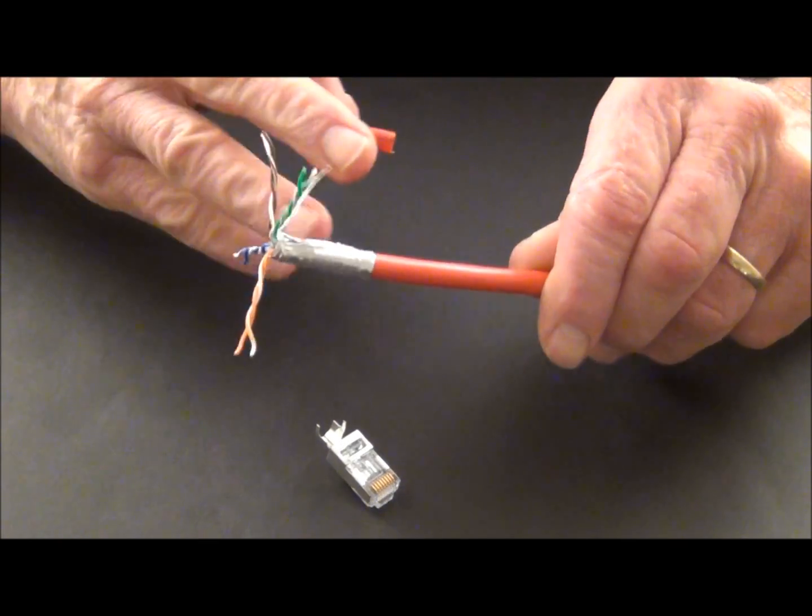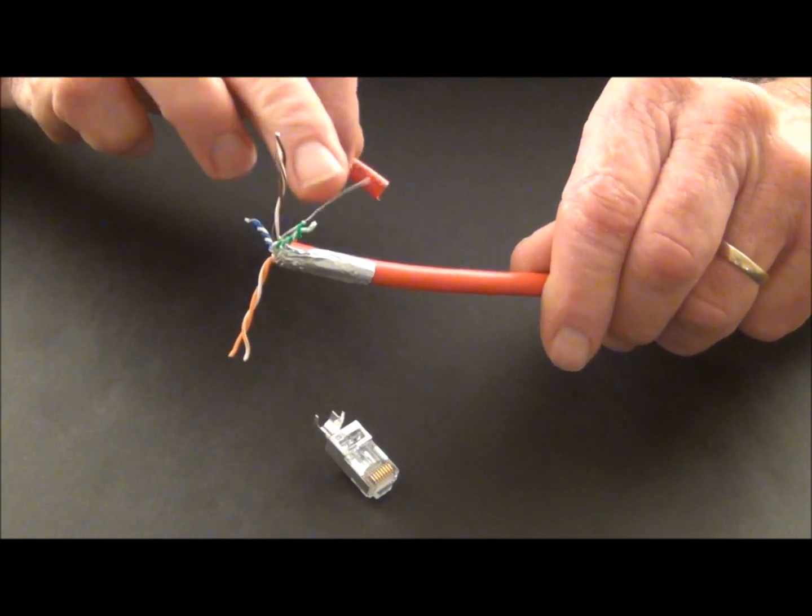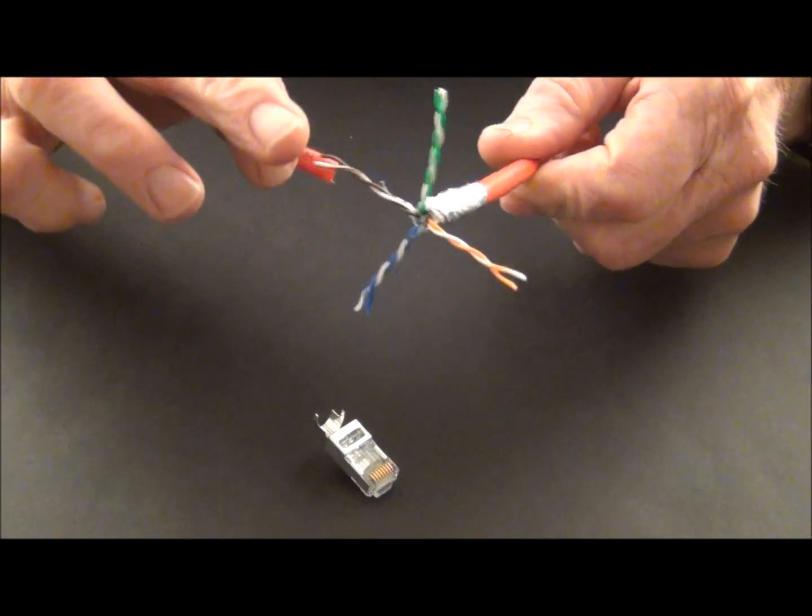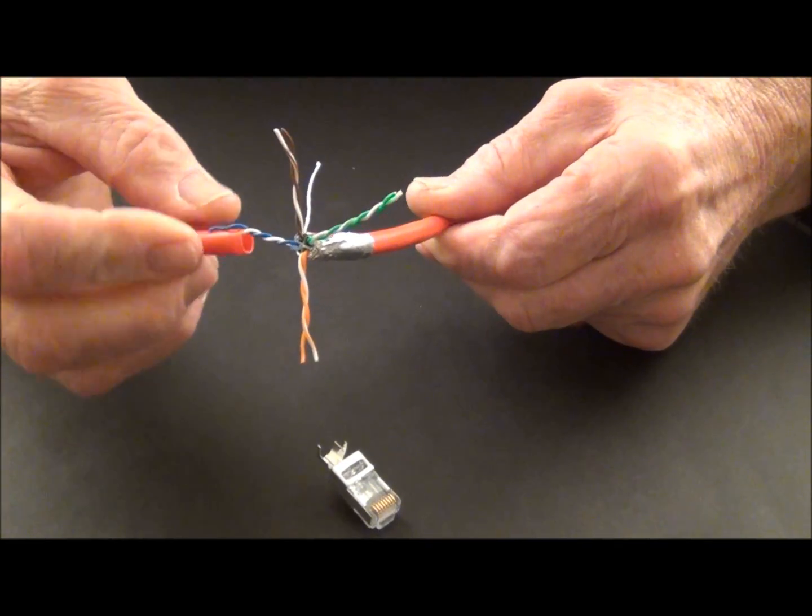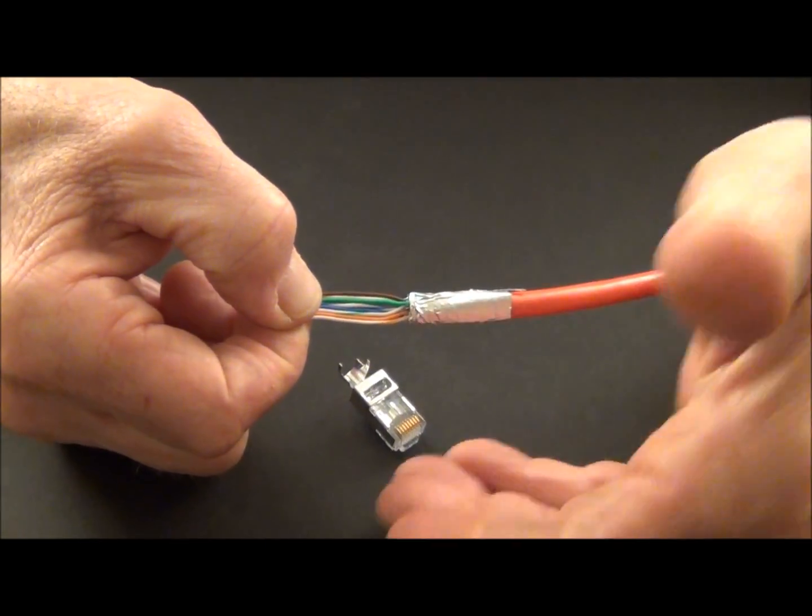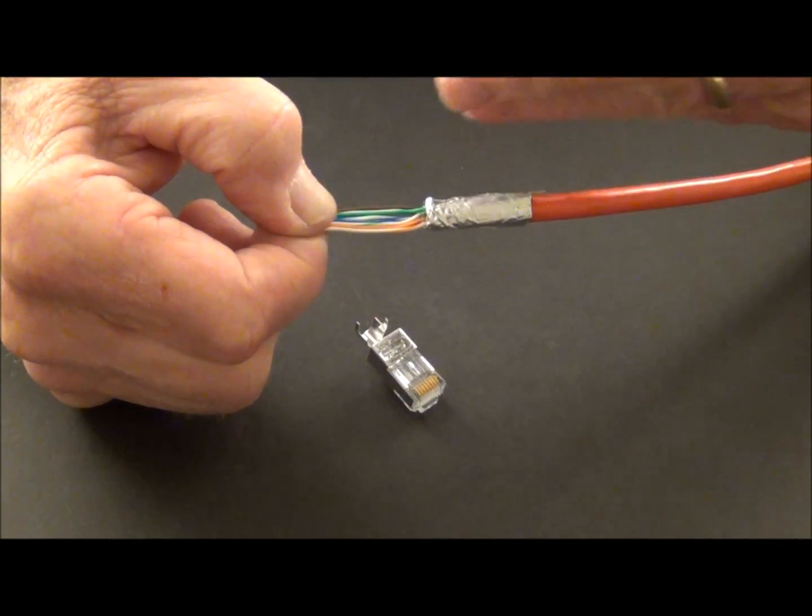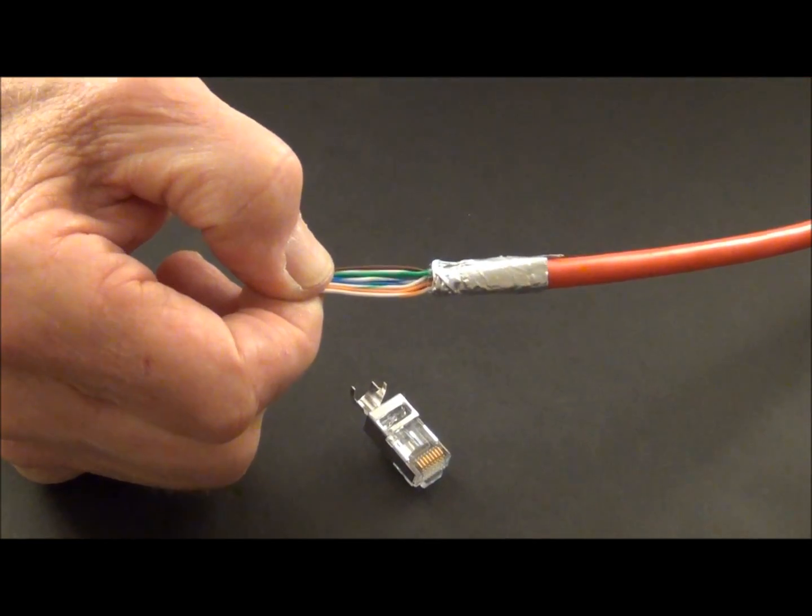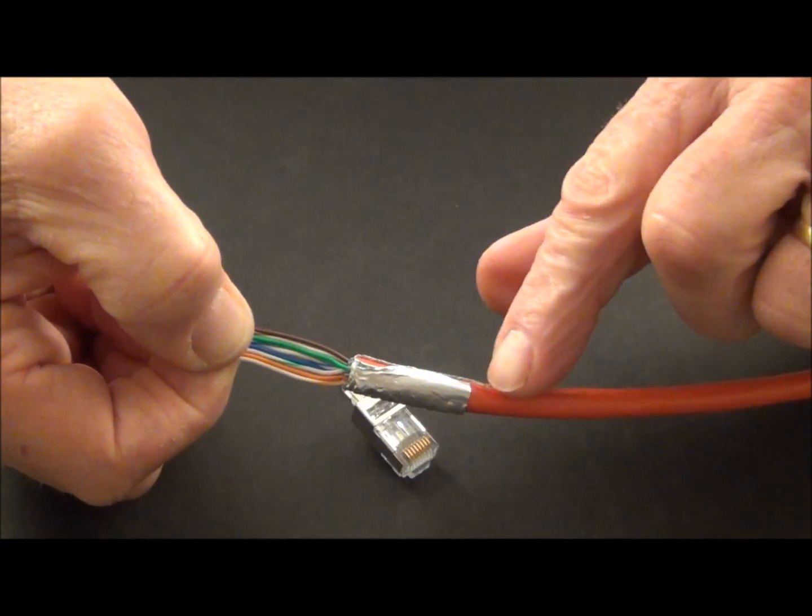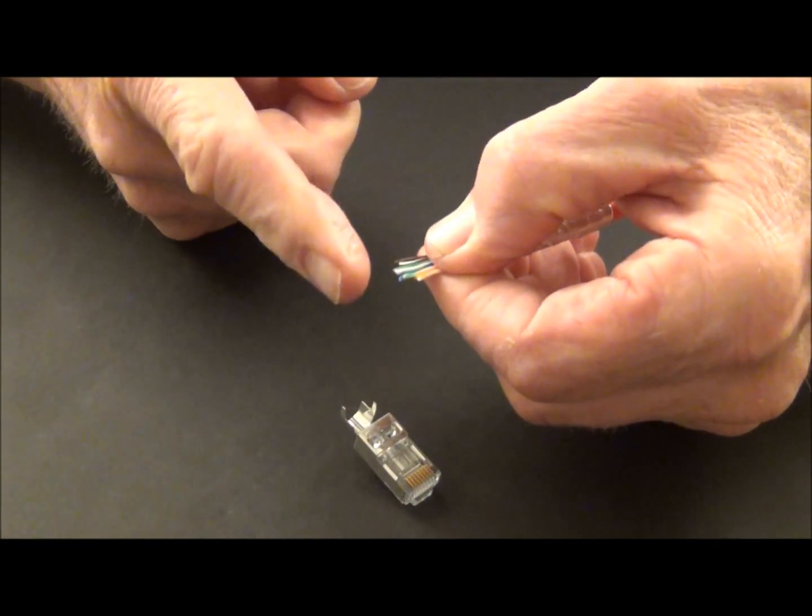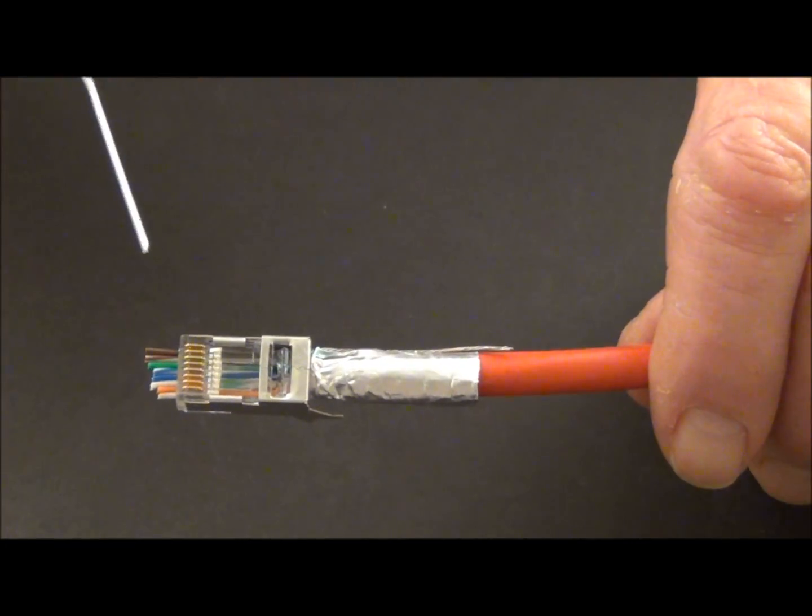And I like to use my little flush cutters. And we're going to come in and trim it. And then remove it. So the foil, I've kept intact. Brought it down to the end of the jacket. Folded it all the way back. I've twisted my drain wire so that the strands are all together. And then I've separated my pairs. And now the next step is separating the pairs. So let's separate the pairs. Okay, I've combed out my kinks and my conductors. I laid them out. I'm doing the B. So I start with orange-white, end with brown. And of course, my foil is in place, my drain wire.